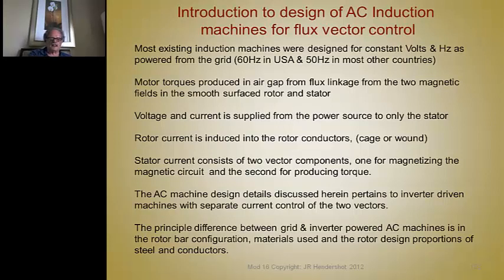So what an inverter does is take those two current vectors apart and control them separately. So what we want to do is discuss what characteristics of the rotor design have to be optimized, and what do we need to do to them that's different with respect to a motor that's going to be controlled with a current of two vectors, and not allow it to be done automatically by the fixed frequency, fixed voltage, slip, and changing loads.